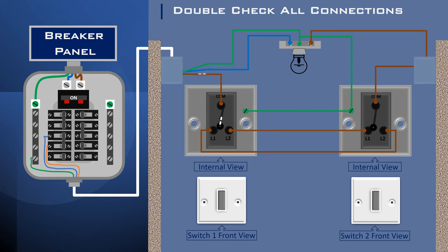Turn on the power supply at the main breaker panel and let's analyze the flow of electricity to the light fixture between switch 1 and 2. With the switches in the position shown, the electricity will flow from the first switch L1 terminal to L2 terminal of switch 2 where the circuit is broken. If we change switch 1 position, the electricity will flow from the common terminal wire through L2 of switch 1 to L1 of the second switch through the light and back to the neutral wire.